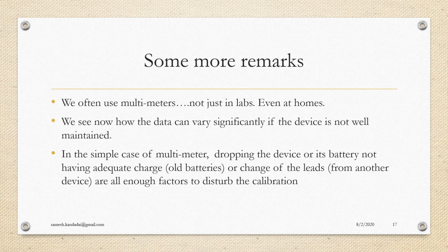Multimeters are used at home and in labs, and the calibration of a multimeter can be disturbed just by dropping the multimeter on the floor. It need not break. Just by dropping it, it can change. Or using old batteries inside the multimeter, or changing the leads from one multimeter to another, because the leads have set resistance values, and if you change them, the end result is going to differ even if microscopically.